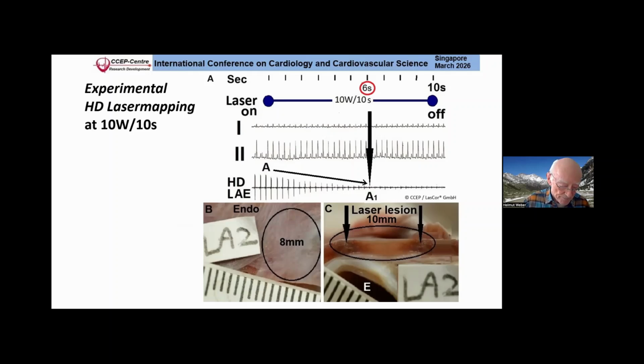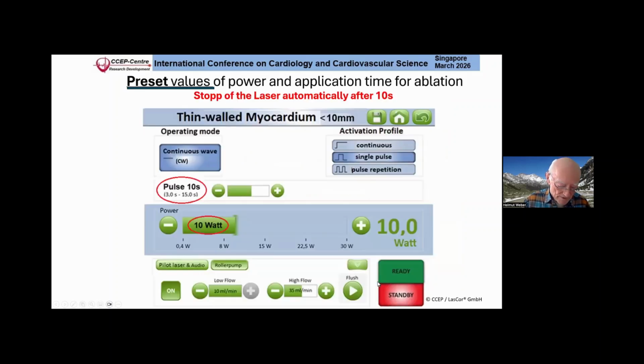High-density laser mapping guided posterior wall isolation achieved permanent abolishment of atrial potential amplitudes in 6 seconds. A transmural endocardial lesion was 8 mm in diameter and was without esophageal damage. For safety reasons, to limit lesion growth to the atrial wall, the energy setting was preset to 10 watts and 10 seconds. Therefore, the laser was stopped automatically after 10 seconds or by releasing the foot pedal.